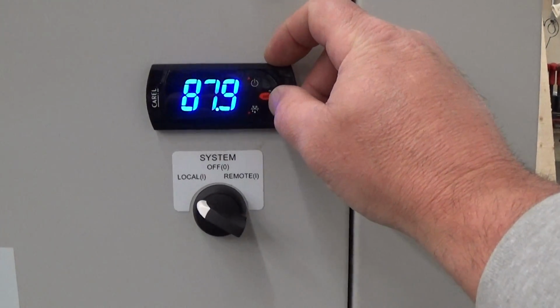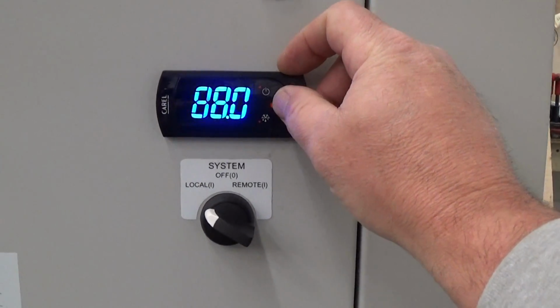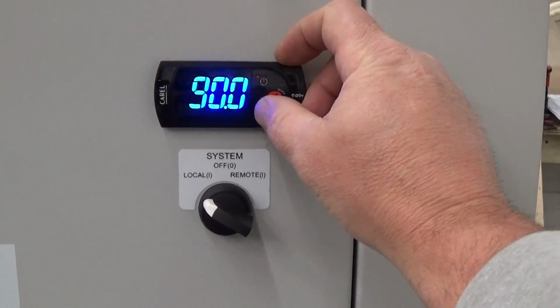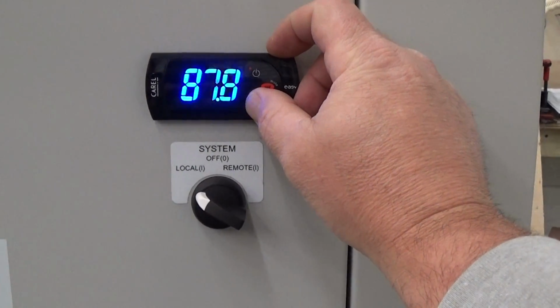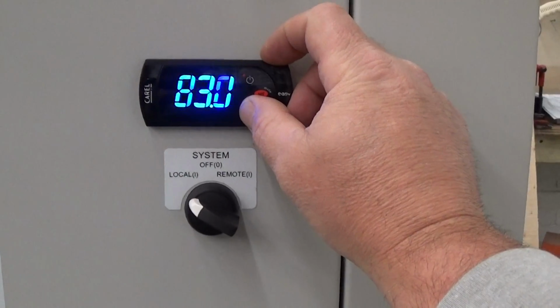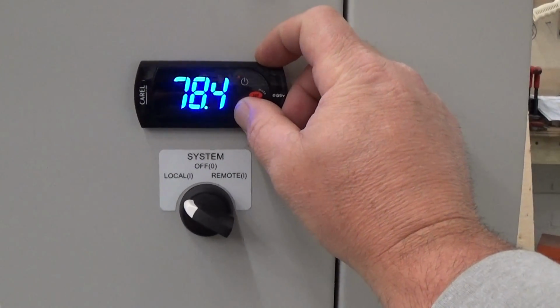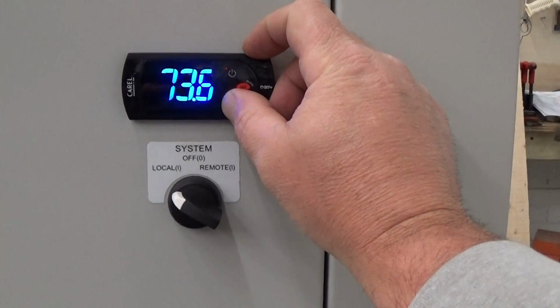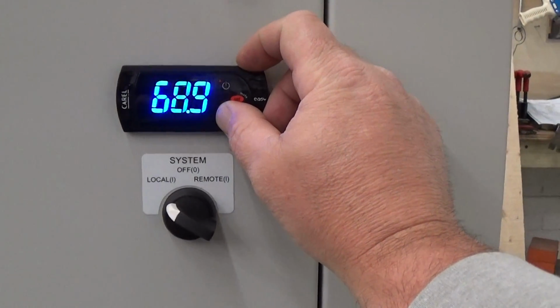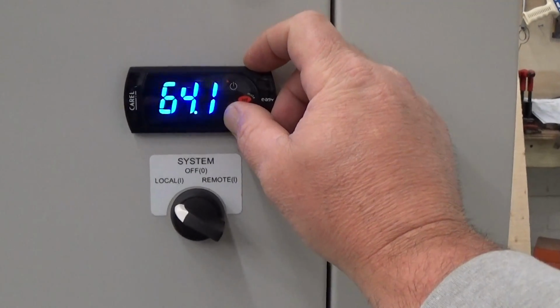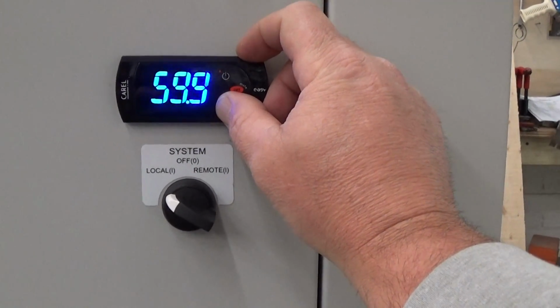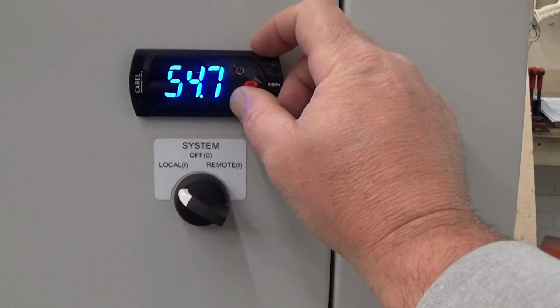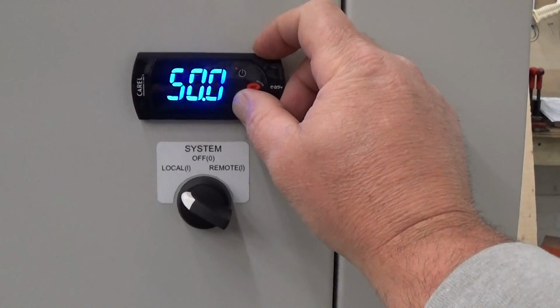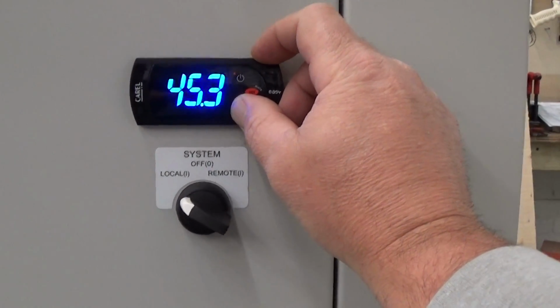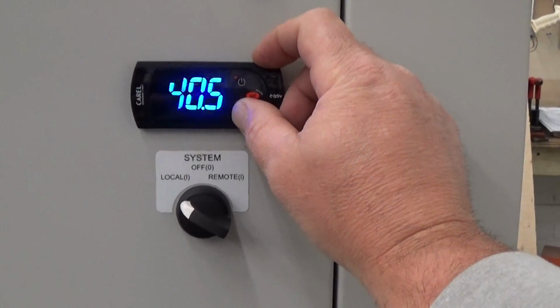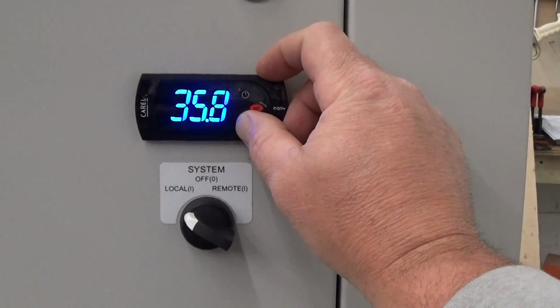To change the set point, you just hold the set button for a second. You have it at 90 right now. We're going to bring it all the way down to 30. In fact, we got into the guts of the program and checked the pressure switches to make sure it can accommodate this, and we've run it for a couple days. There are other parameters inside the controller, actually many. You really don't need to go into any others, although that information will be posted on our website.